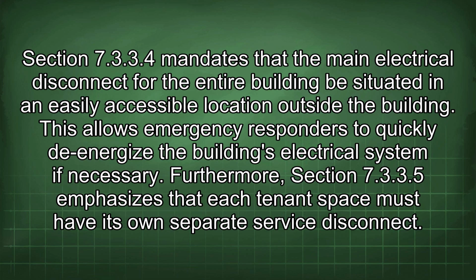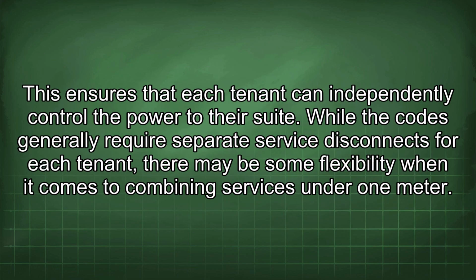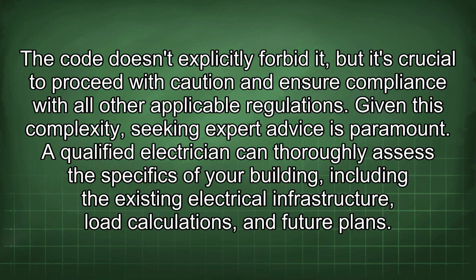Furthermore, Section 7.3.3.5 emphasizes that each tenant space must have its own separate service disconnect. This ensures that each tenant can independently control the power to their suite. While the codes generally require separate service disconnects for each tenant, there may be some flexibility when it comes to combining services under 1 meter. The code doesn't explicitly forbid it, but it's crucial to proceed with caution and ensure compliance with all other applicable regulations. Given this complexity, seeking expert advice is paramount.